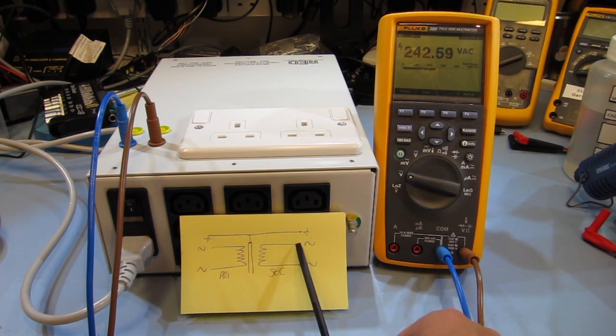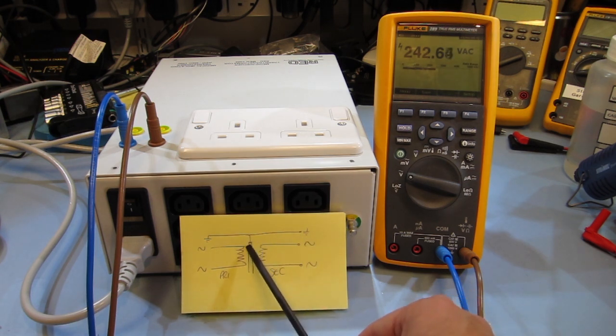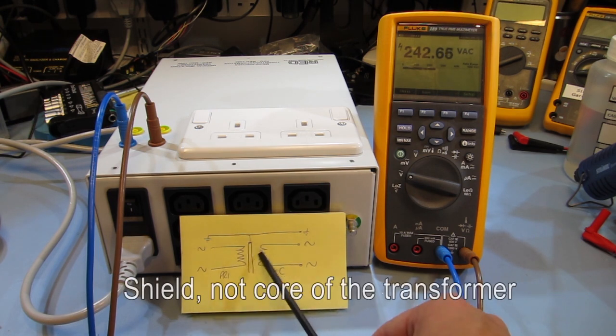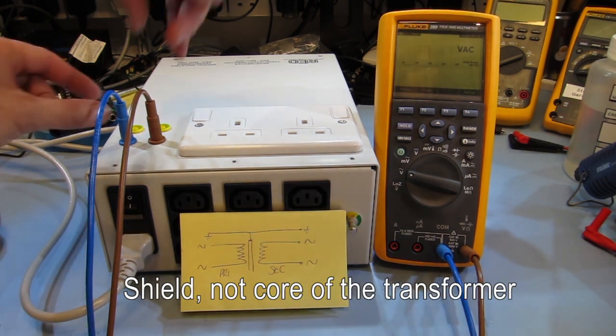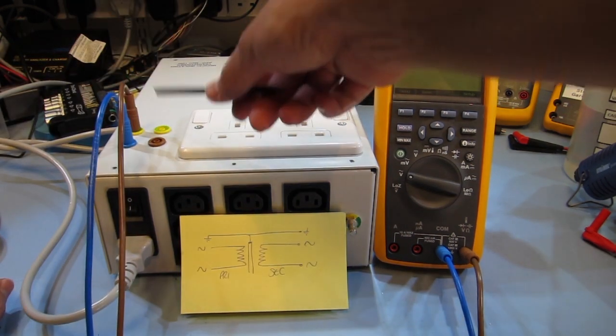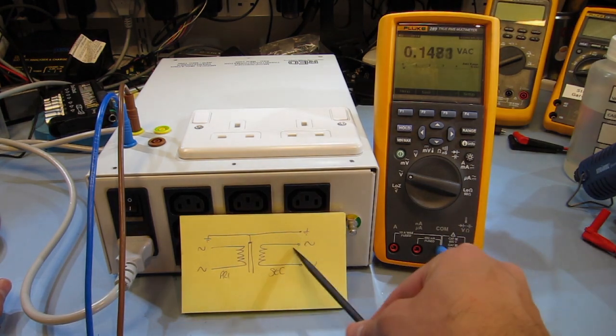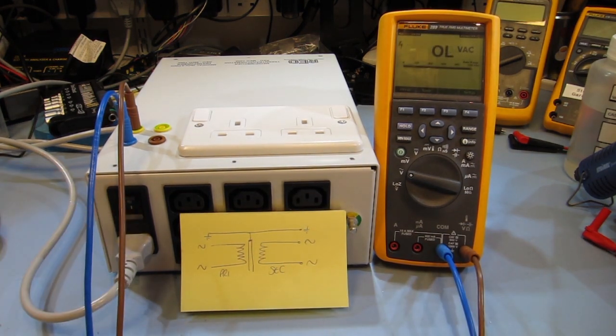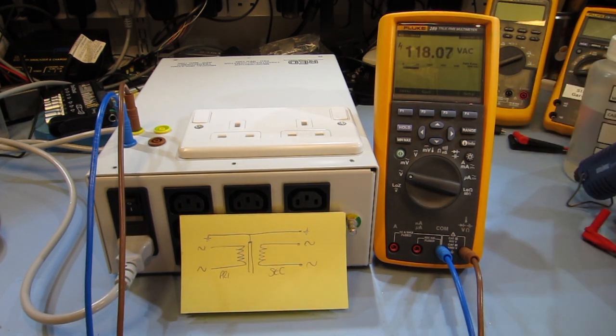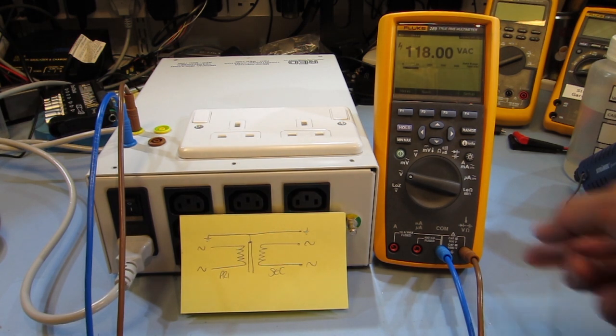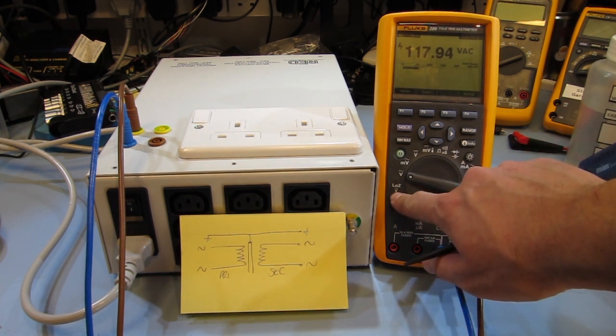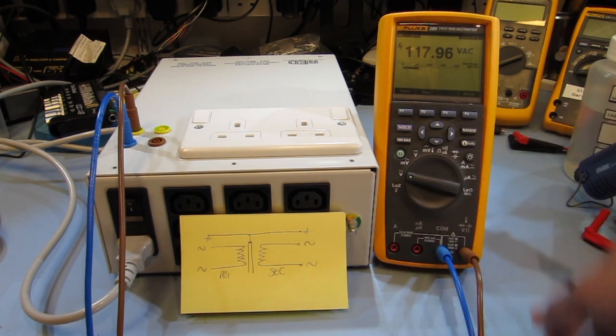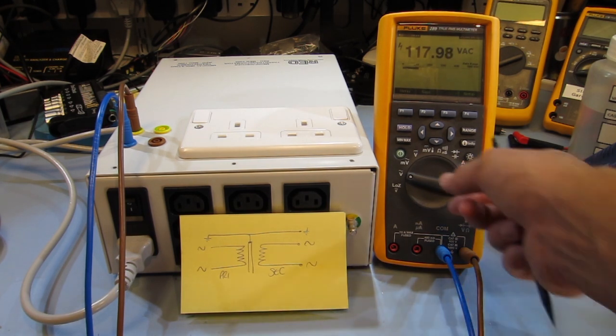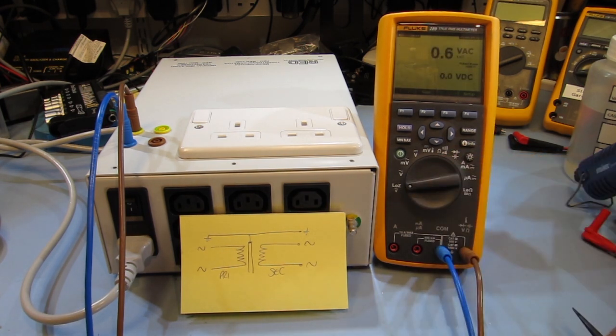So I'm curious whether we can read any voltage between the output of here and earth, because we are going to have a small amount of capacitive coupling between the shield of the transformer and the secondary. So if we just move one of the jacks to the earth, so we're reading between here and here now. If we turn that on, we are reading about 118 volts, probably at a very low current. We do have a low impedance measurement mode on the Fluke 289, so at the moment it's reading with possibly 10 meg input impedance. If we switch to the low impedance mode, we're reading basically nothing here, 0.6 volts.